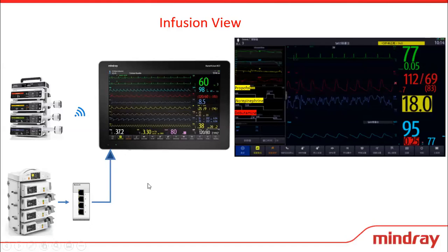In the infusion view, this is just software that is put in our patient monitors, and we use this software with our pumps. We have the new model called the N-series pumps, which are connected to our patient monitors directly using Wi-Fi, or the old model called the SP, the Benefusion pumps, where you use a module called the Benelink module to connect to our patient monitors.